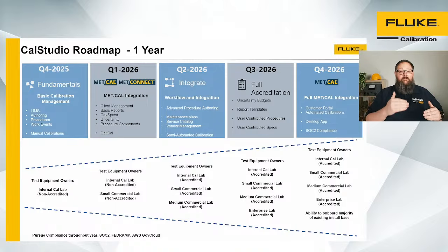for a given parameter and function, which instruments can support that, of a given range or a given way to do that measurement at a really granular level, and then mapping those together to say, for this procedure, I need a device that can generate this type of signal with this type of uncertainty, and then finding which devices we have configured or available that support that.